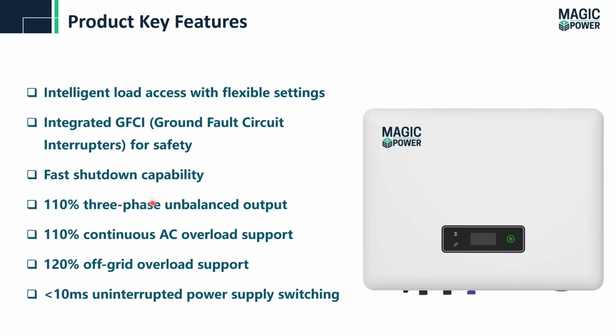110% three-phase unbalanced output for phase A, B, and C. 110% continuous AC overloading support for the system, and in case of off-grid, up to 120% overload support. And if we talk about the switching time, it's less than 10 milliseconds, which is uninterrupted power supply switching.